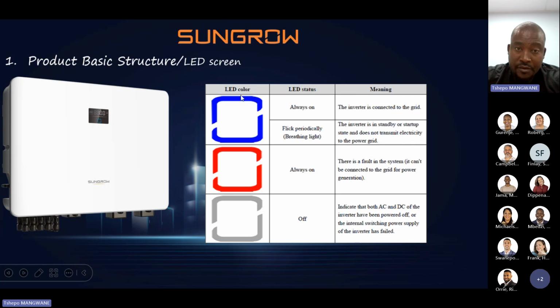Okay, so the first LED indication, if it's always on, the inverter is connected to the grid and the power is being transmitted from DC to AC side. So that tells us what? The inverter is on operational mode, okay? But the moment that the inverter starts flashing in slow motion in the blue light, you just know that the inverter is on standby or starting up.